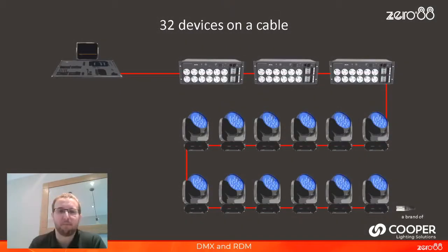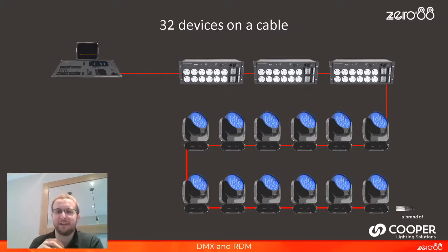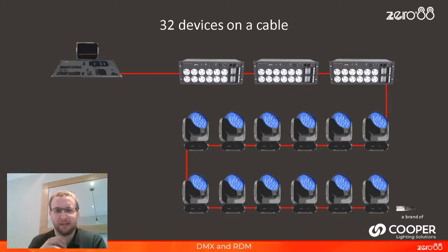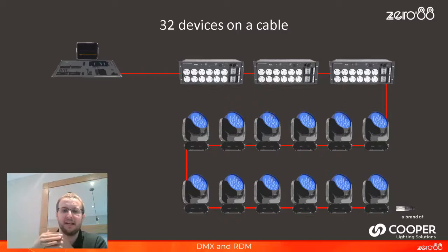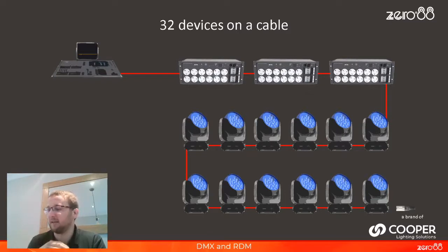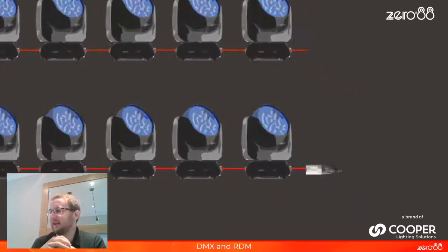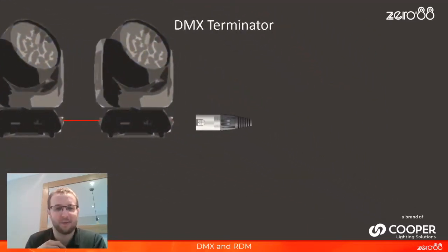This is the topology of a DMX network — just a word for how you wire it up. We come out of the lighting console and go through whatever devices we have. In this setup, beta packs take up six channels each, so 18 channels on the top row. Moving lights could easily be 20, 30 or 40 channels each. So you can see we're near our 32-device limit and close to our 512-channel limitation. At the end, we have a Terminator.